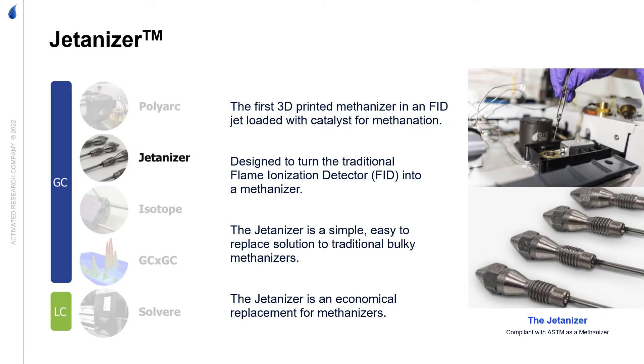The Jetanizer is a 3D printed FID jet that is packed with a reduction catalyst. It replaces a standard FID jet but can convert carbon monoxide, carbon dioxide, and formaldehyde to methane for detection. By utilizing the FID heater and hydrogen flow control, no additional parts are required.